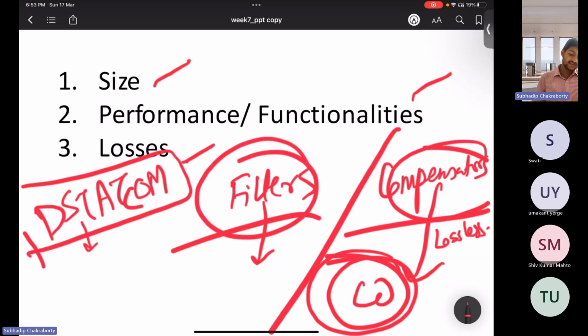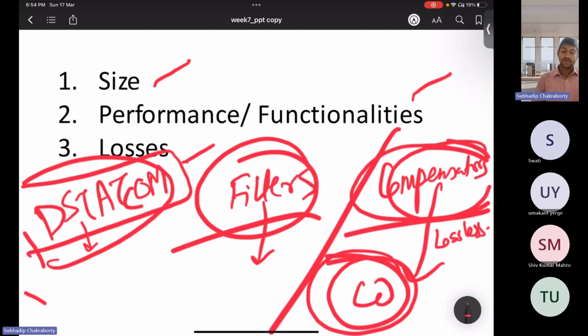So what is the difference between filters and the DSTATCOM? The DSTATCOM can compensate for the harmonic components if you apply some direct control techniques, but it does not filter out the harmonic components. Please understand the difference. The DSTATCOM can feed particular currents into the system, like harmonic components, such that the harmonics don't reflect at the grid side, but it is not eliminating or filtering out the harmonics from the load currents. So compensators can only compensate for reactive power or some harmonic components, but to extract or eliminate them from the system, the filters can do that.